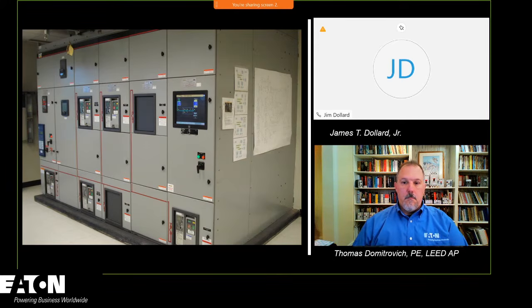I don't know what happened, but when you're doing an arc flash risk assessment in 130.5, it tells you that you always have to do an arc flash risk assessment. But the very first thing you need to do is determine if there's an arc flash hazard. That's the key — you must first determine if there is an arc flash hazard.